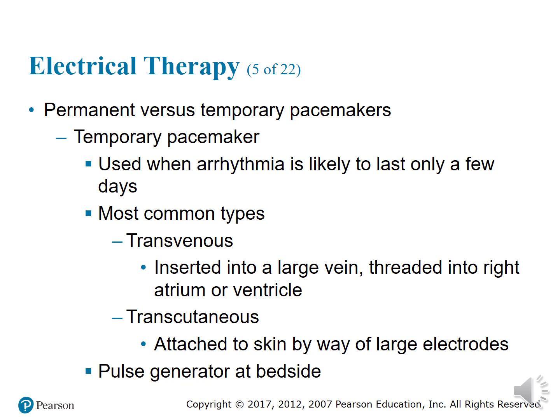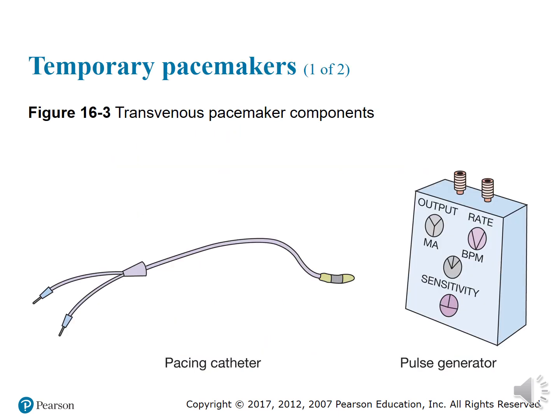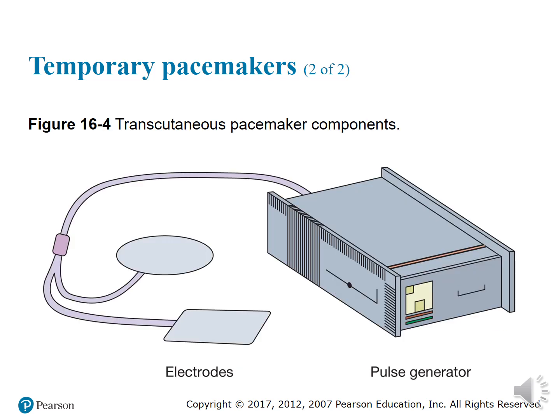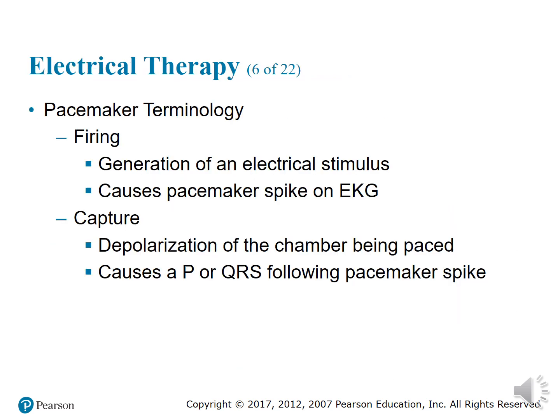The transcutaneous pacemaker involves large pacing electrodes that are attached to the chest and back to help pace the heart through the chest wall. Both temporary pacemaker methods use pulse generators at the patient's bedside. Temporary pacemakers should have batteries, pacing thresholds, and connections between the pacing leads and generator generally checked. And these are the different temporary pacemakers that they have.